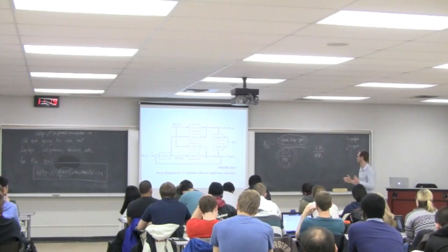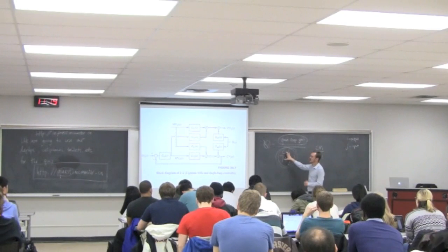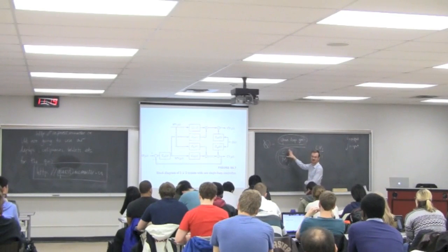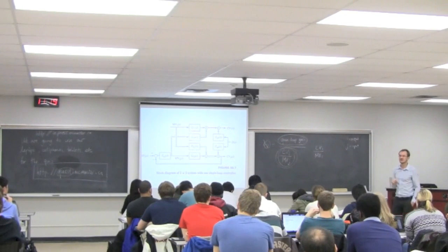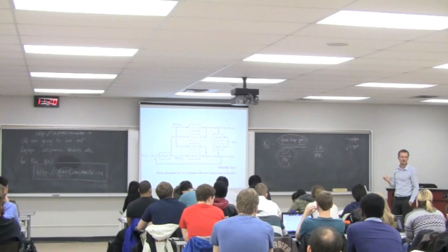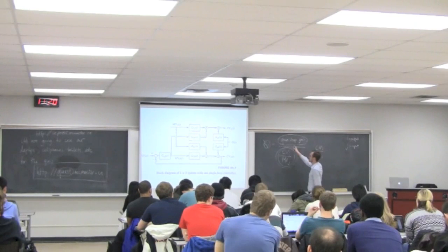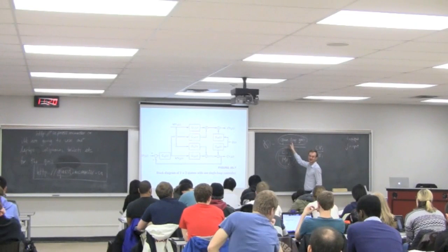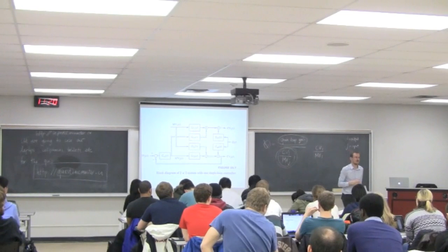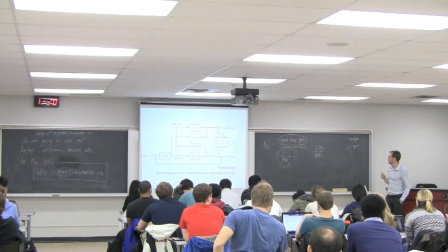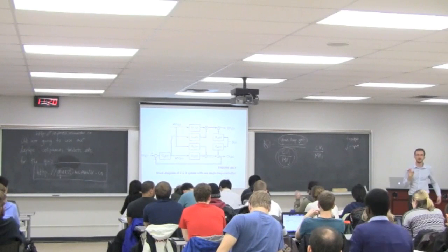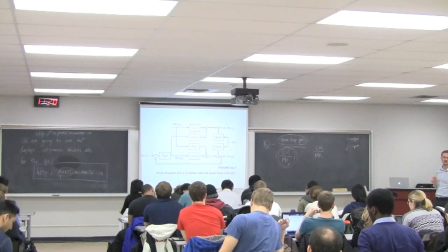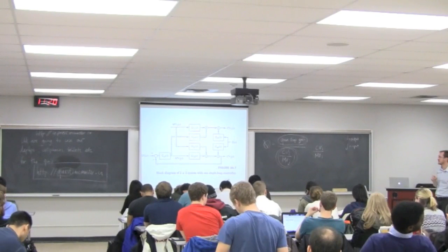Now that's not a bad thing, because the loops are normally closed and you can go change the sign of your controller's gain to match that gain. But never believe that the loops always remain closed. Control systems fail. And if a control system fails, that means the loop opens up. And then you suddenly have a case where your gain switches on you, your other feedback controllers are still active, and you can create an unstable result. So we try to avoid pairing on negative lambdas, because it's telling you your process is going to switch sign on you if something goes wrong. We don't like that risk of instability.